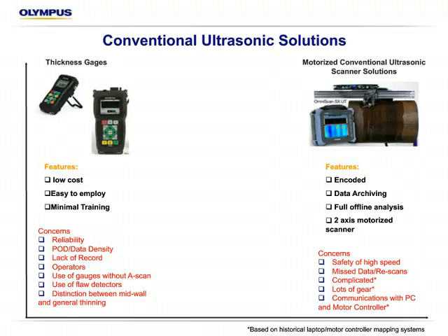Again, those really go back to the old ways. Now, like shown here with an OmniScan, conventional ultrasonic, and the motor controller, not really a lot of connections. It's just an encoder in. But when you go back to the dedicated laptop for running an operating system connected to a motor controller, connected to a scanner, there were quite a bit more connections and a lot more complication to the whole process.